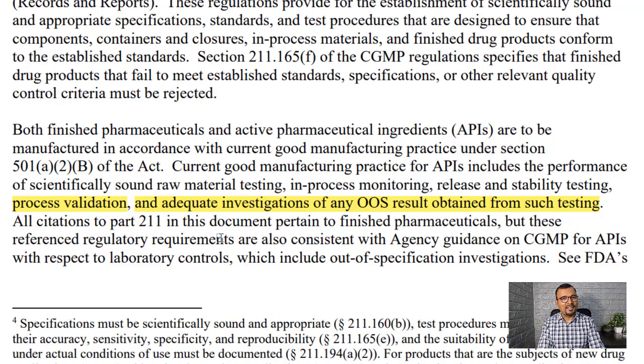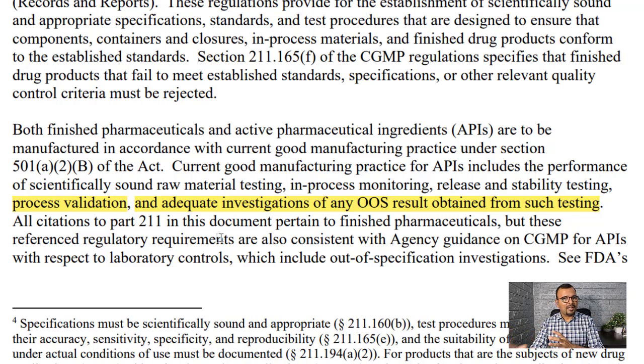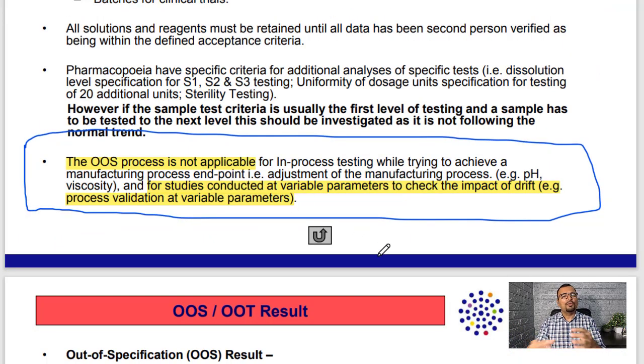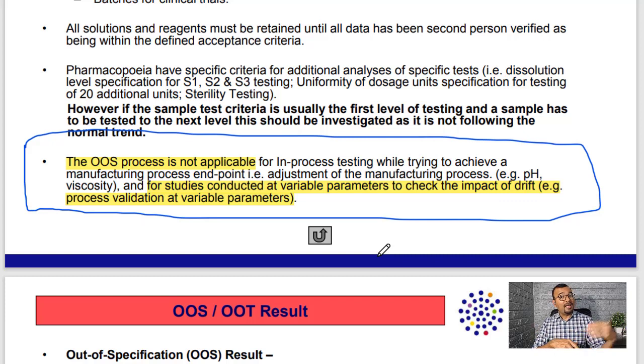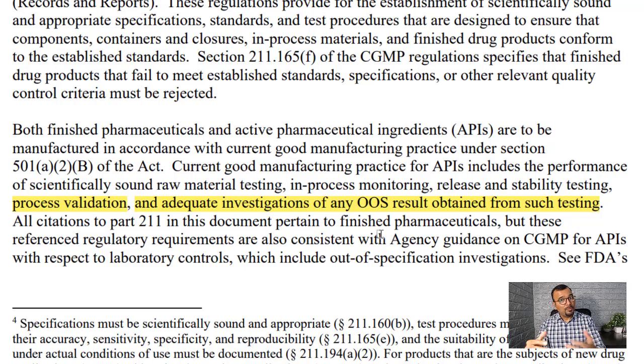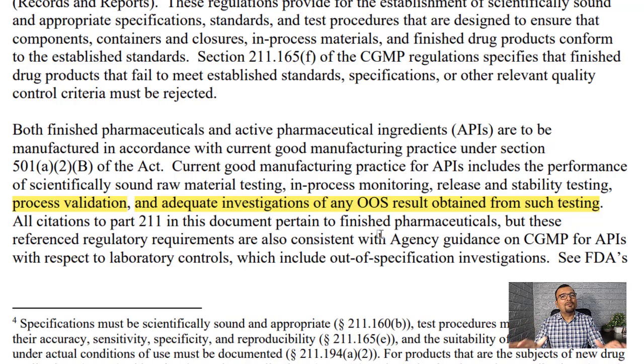The final question is: how can one deal with such a situation? If an out-of-spec result is observed for variable parameters, shall we go with the OOS process or another QMS process? According to MHRA, it is clear you need not investigate by the OOS process, so you can adopt alternative processes like deviations or lab incidents. But as there is no clear-cut guidance on this point in the US FDA guidance document, and to be on the safer side, it is always advisable to investigate the out-of-spec result — irrespective of whether it is an optimized or variable parameter — by following the OOS process.